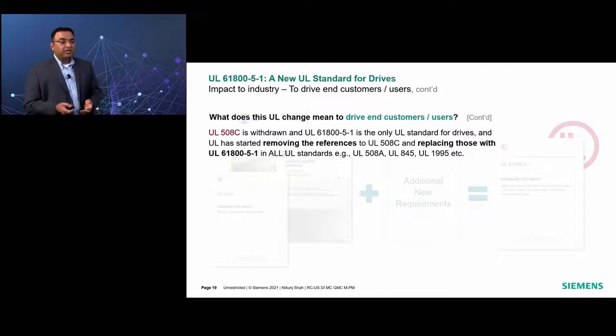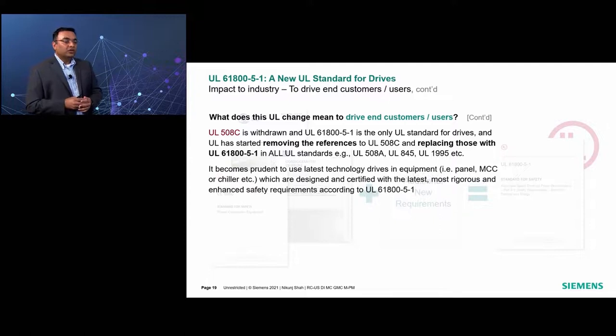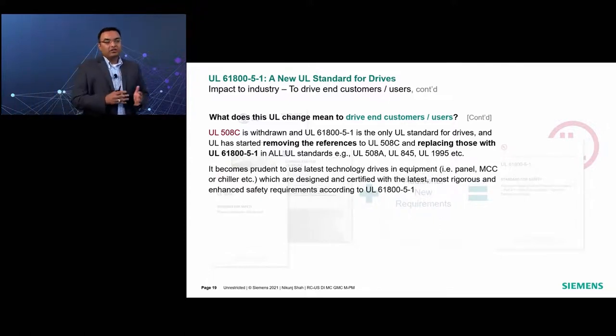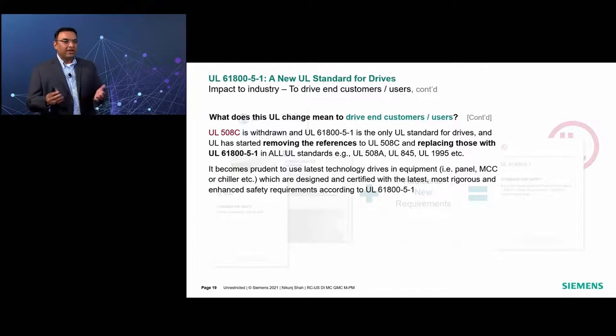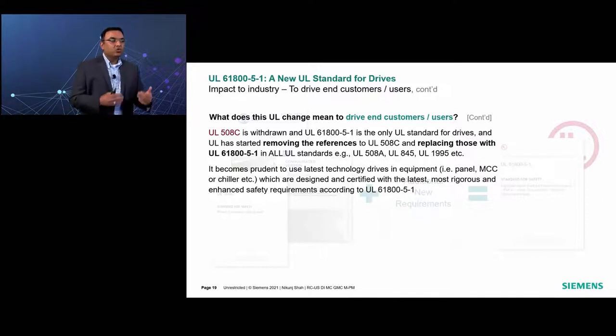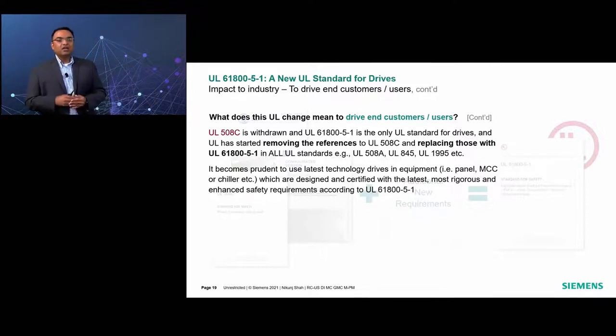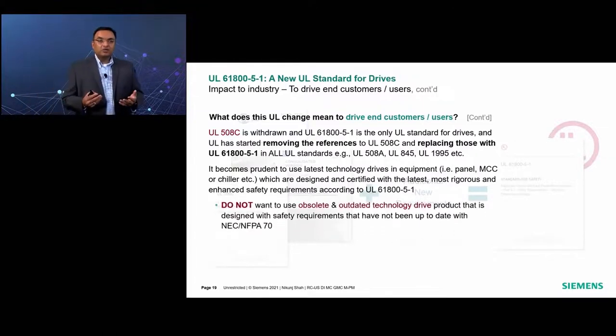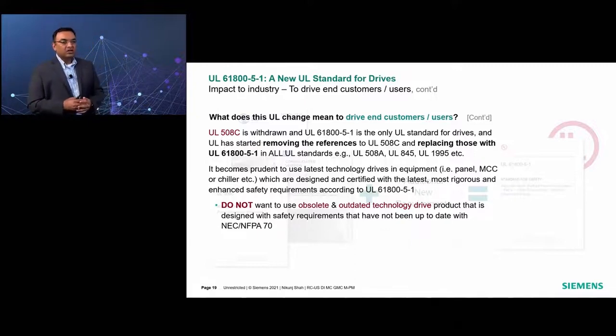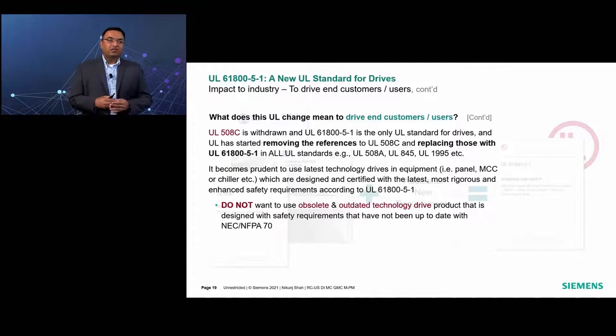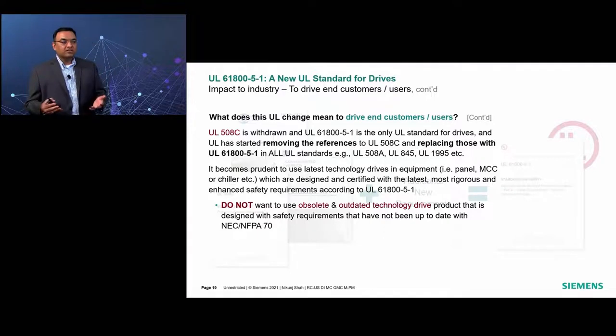there are many others. So it becomes really prudent for the customer to use the latest technology drive products in the equipment in their panel or MCC or chiller, which are designed and certified according to the latest and most rigorous and enhanced safety requirements according to UL 61800-5-1. If I were a customer, I would not like to use the obsolete and outdated technology drive product that is designed with safety requirements that have not even been kept up to date with the National Electrical Code requirement, which is NEC or NFPA 70, in my equipment.